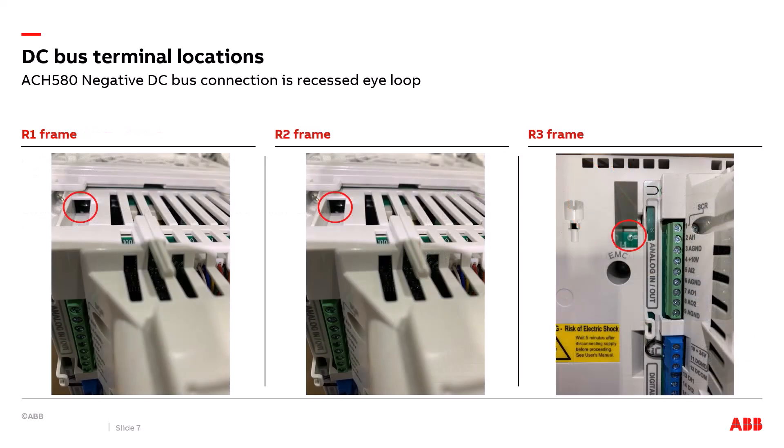The below three images represent the ACH 580, R1, R2, and R3 frame drive's connection point for the negative DC bus. In the red circle on each image there is a recessed eye loop. That is the connection point that you need to connect your voltage probe on your meter to access the negative side of the DC bus.